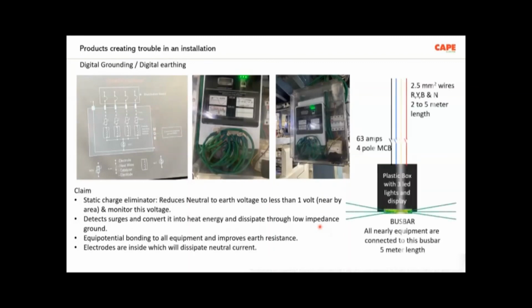But actually what they do is they short the phase and neutral inside this particular device, violating not only the regulation, but all the safety regulations and all the safety standards. I would recommend, if you use this kind of device, please remove it immediately. These devices can create harm anytime. It can create a shock hazard in your building, it can create a fire hazard in your building, it can create a failure of electronics in the parallel circuits. Please understand, you are using this device for one circuit, and probably for that circuit the problems are camouflaged for a certain time, but problems will come on the other circuit. So rather than protecting, we actually use devices which are inviting problems.